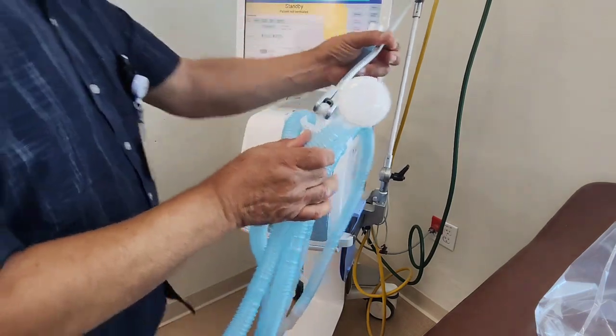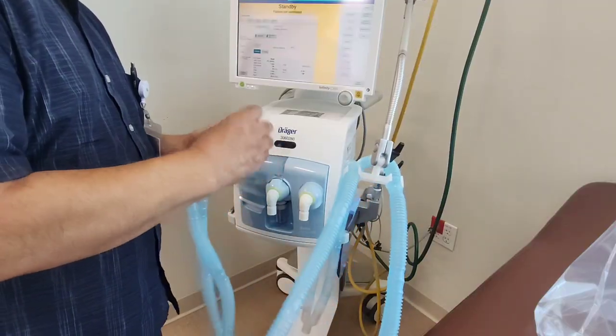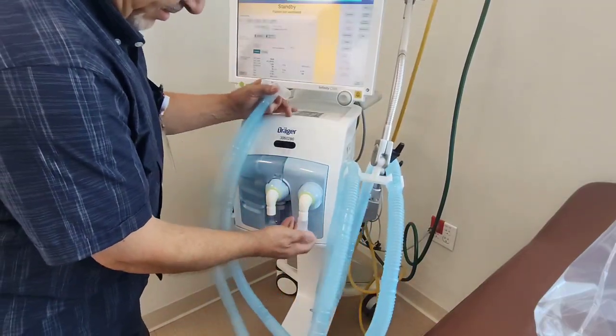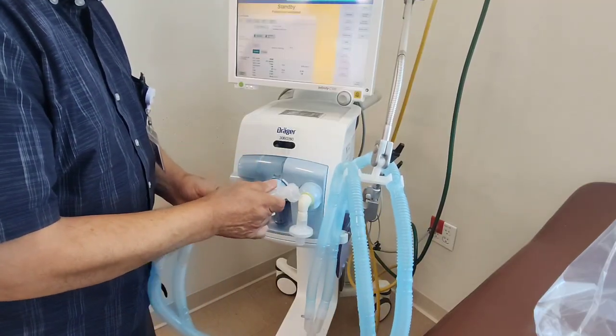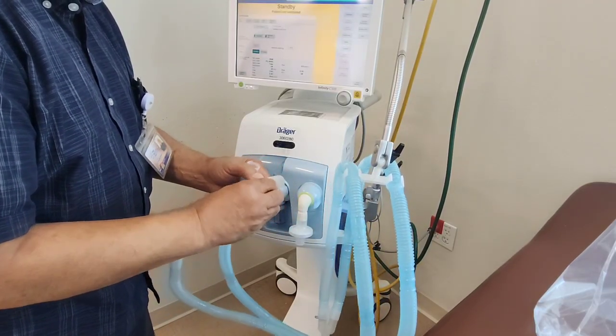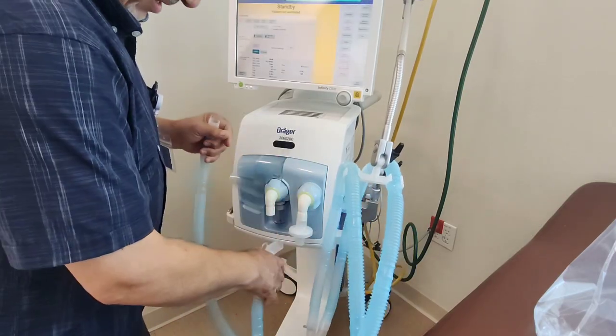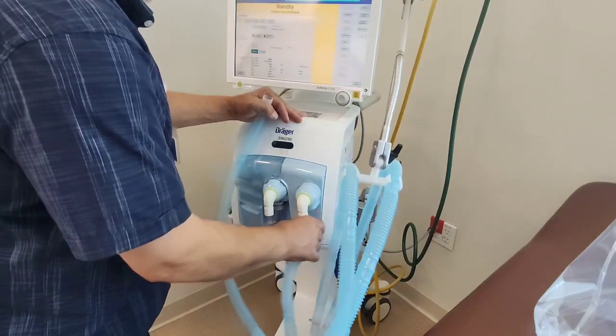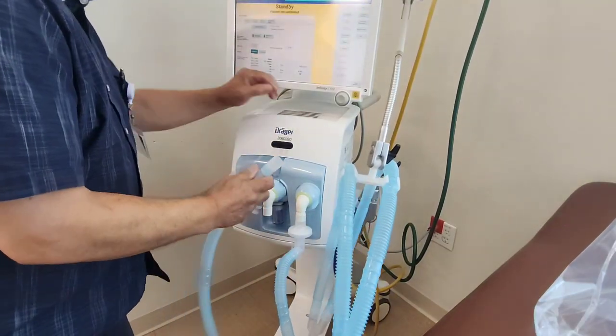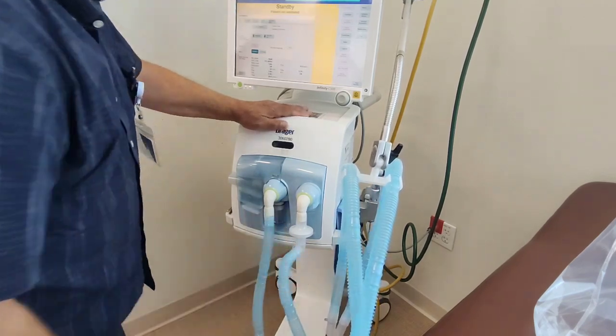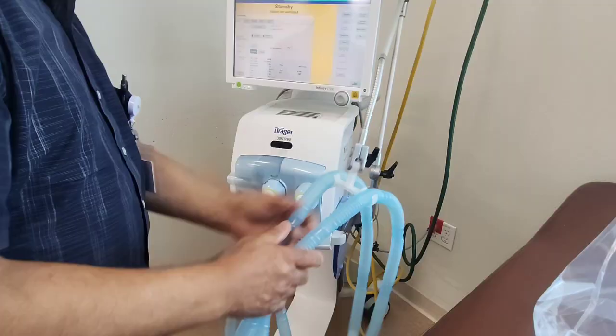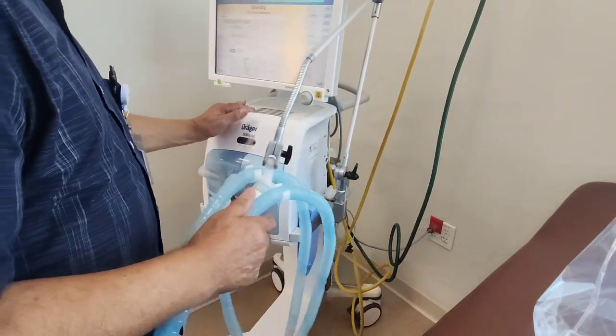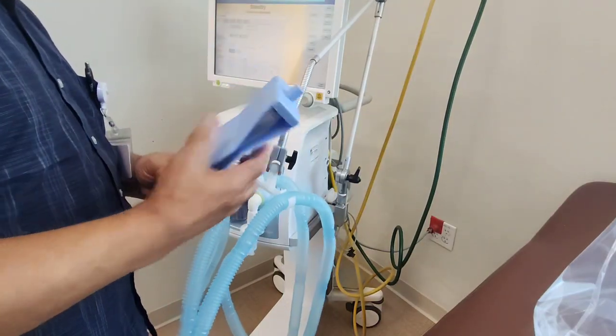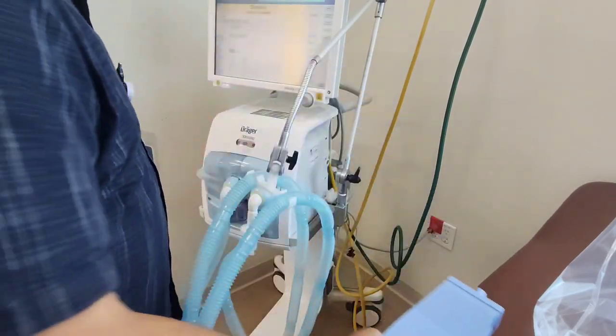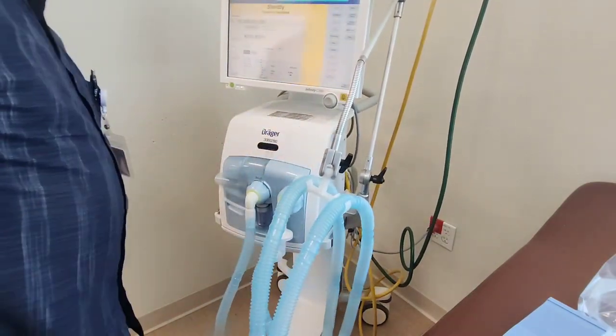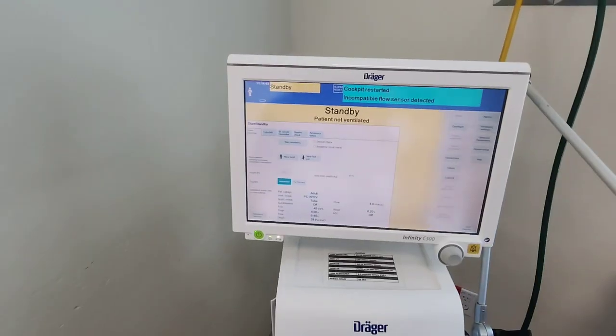So I have my, let's move that out of the way. So I have my filter here, it's a bacteria filter, and I was telling you this is the inspiratory side. This is going to connect here. This is again the side where we could put a temperature probe right here. This is inspiratory, and I'm going to connect it on the bottom. And it does swivel, so don't worry about that. Okay, and this is the exhalation port, will go right here. So that's pretty much hooking up the circuit on the Draeger. It's pretty simple. You don't want to connect the test lung yet until we've actually set the parameters on the ventilator. And so let's look at the screen real quick so you can get familiarized with what the screen looks like.